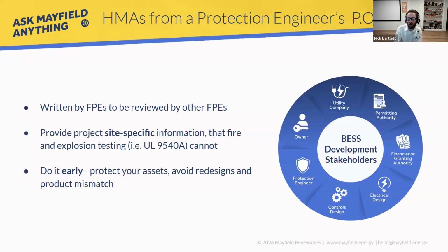My goal is to write a document that the AHJ will approve. Having been an AHJ myself, I want to make sure everything complies. So my goal is to write something that the AHJ will have as few comments on as possible, and in doing so, all those pain points need to be addressed. The AHJ might not want to get into the weeds about the liquid cooling system or the BMS, but they sure are going to want to look at access, water supply, separation distances, and large scale fire testing. It's really the gamut of what goes into these if they're done properly.